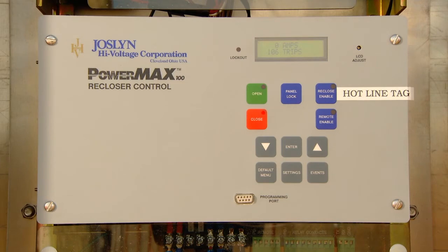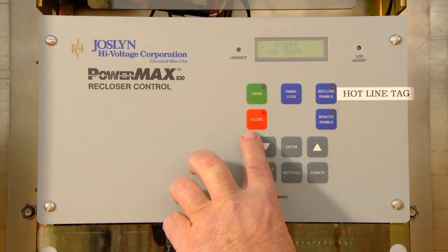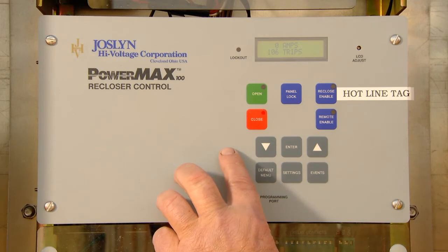Panel lock. Pressing the panel lock button will block all front panel commands except the open button. The button must be held for 4 seconds to change lock status. When the control is locked, the status will appear on the LCD display. The red indicator LED on the Close button tells us that this unit is closed.